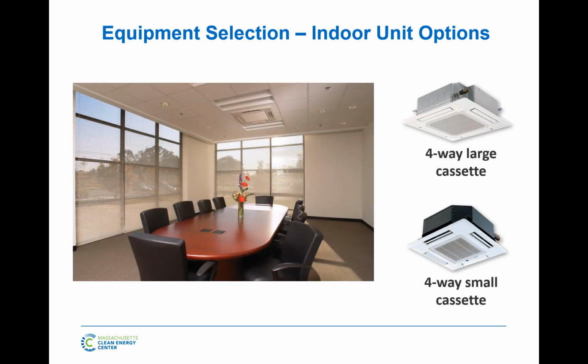A very common commercial unit, especially for office buildings, are four-way cassettes. So these are typically installed in drop ceilings mainly because the small ones do need access from the sides. The four-ways are capable of service access from the bottom. But this is return air through the center of the unit.